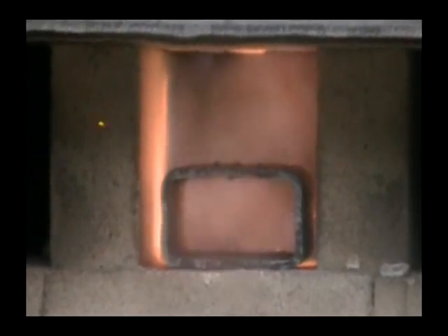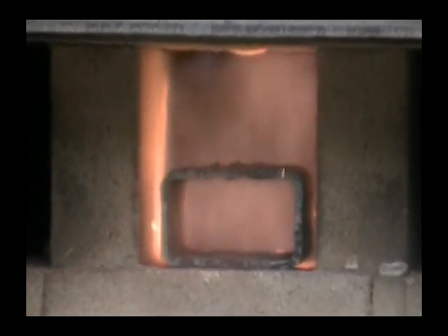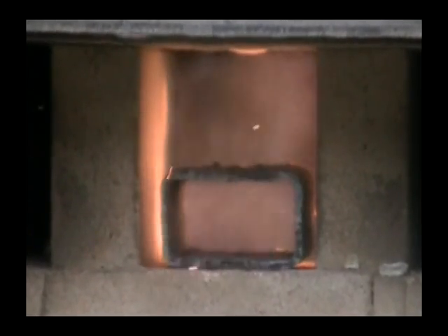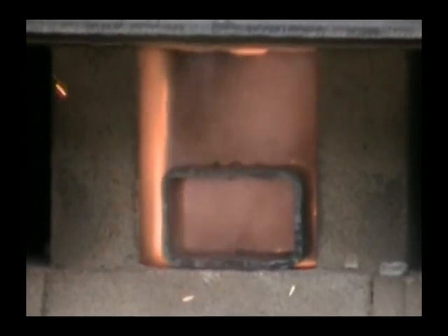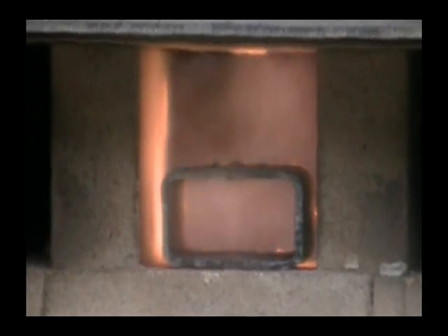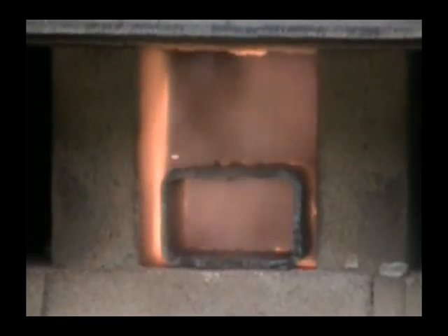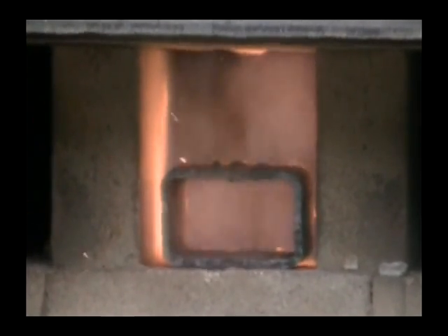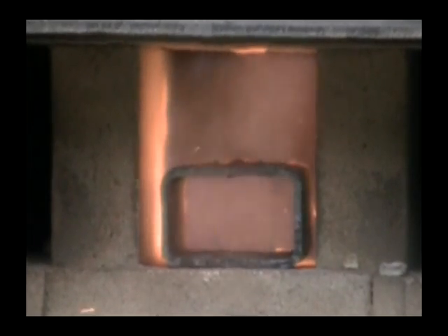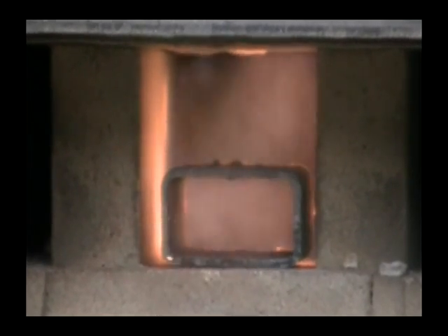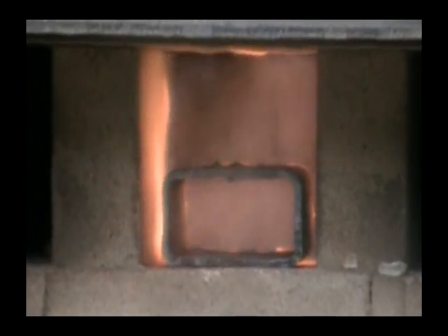The heat has to come out of this reaction gasification chamber that we're watching here, comes all the way to the front of the stove, hits the door, turns around 180 degrees at the door, and starts its journey back through the first pass of the heat exchanger to the back of the stove. We're water cooled on both sides of the bottom of this gasification chamber. We go to the back of the stove and we start up 6 tubes of 2-inch in size where we turn 90 degrees and go to the front of the stove where we do a 180 degree turn and come to the back of the stove.